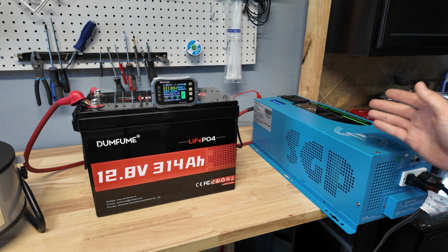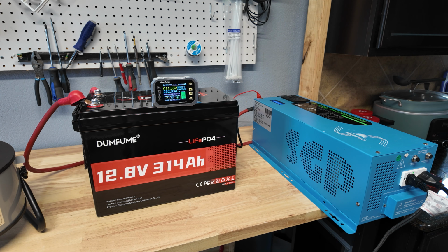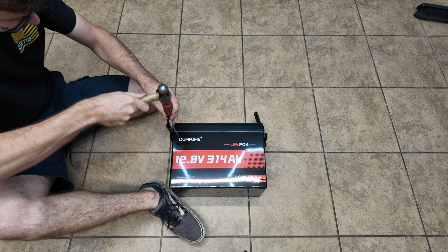It's been running now for a few minutes at 250 amps, and it doesn't look like it's gonna shut off. Even though this is rated for only 200 amps, it's able to support over that. Now it should shut off for safety, but it doesn't look like it's going to, which is pretty common when it comes to budget batteries - a lot of them don't shut off.